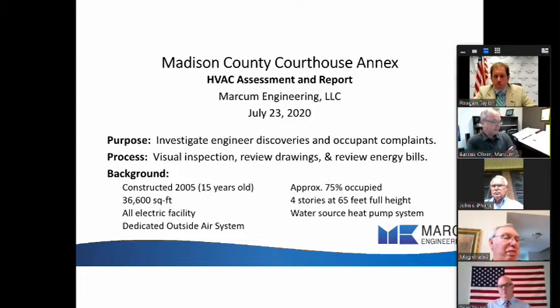So the background of the building, it was constructed in 2005, so it's 15 years old. That's relatively young for a building. It's 36,000 square feet. It's an all-electric facility, which was kind of surprising that we're not using natural gas, being that we have natural gas in the city. It's approximately 75% occupied. I'm not sure the building has ever seen full occupancy yet. It could have, but it's slowly been filling up. When the county clerk moves in, I believe we'll be at 100% occupied.